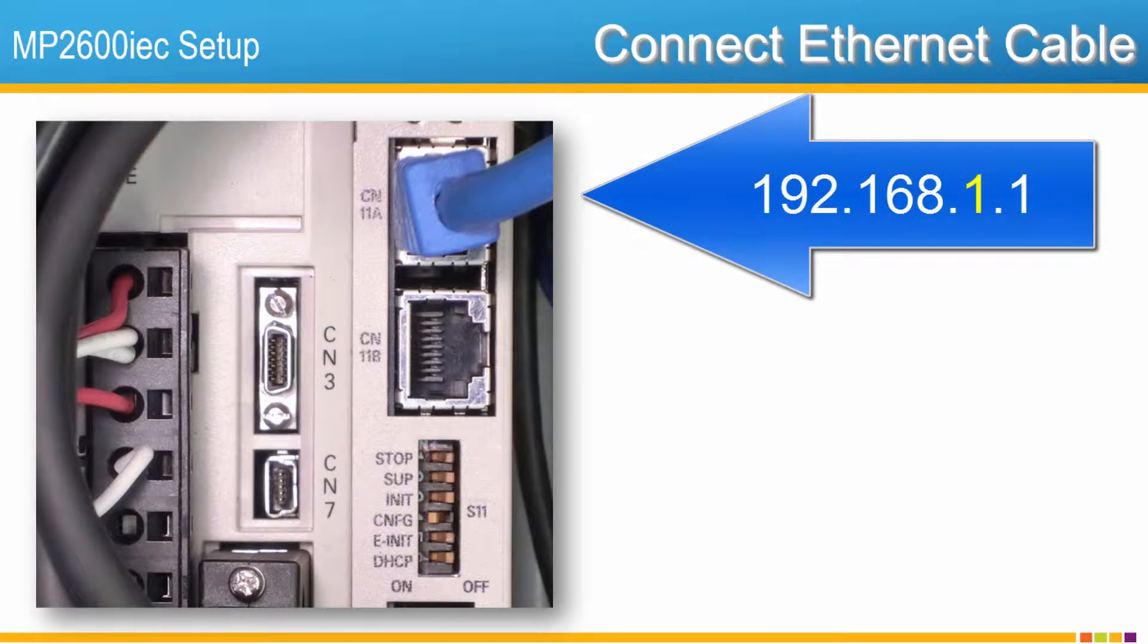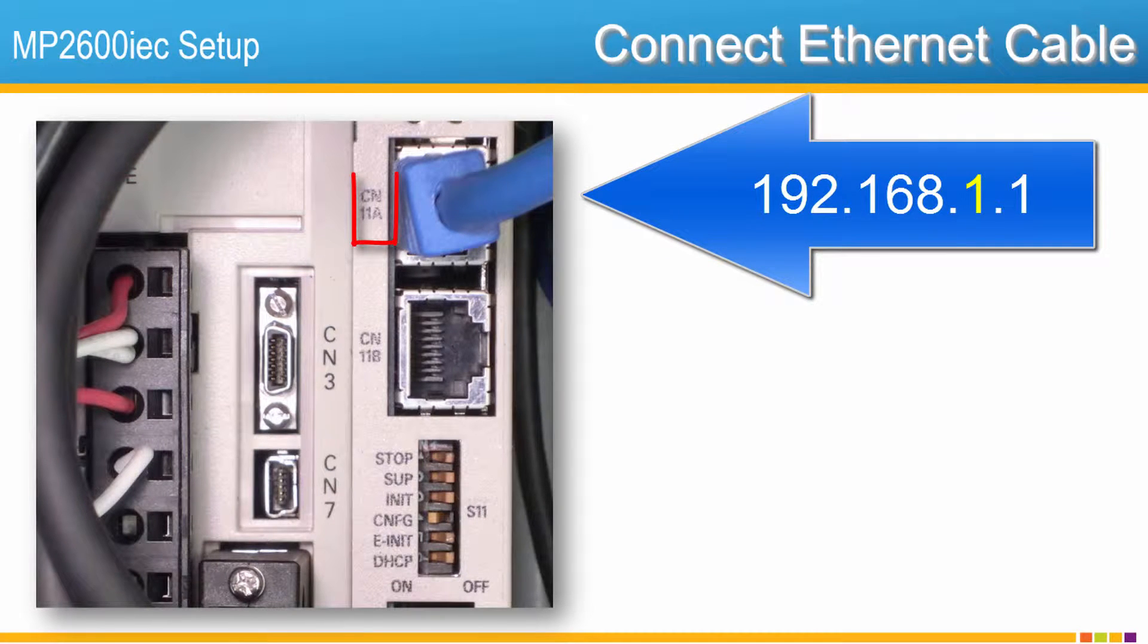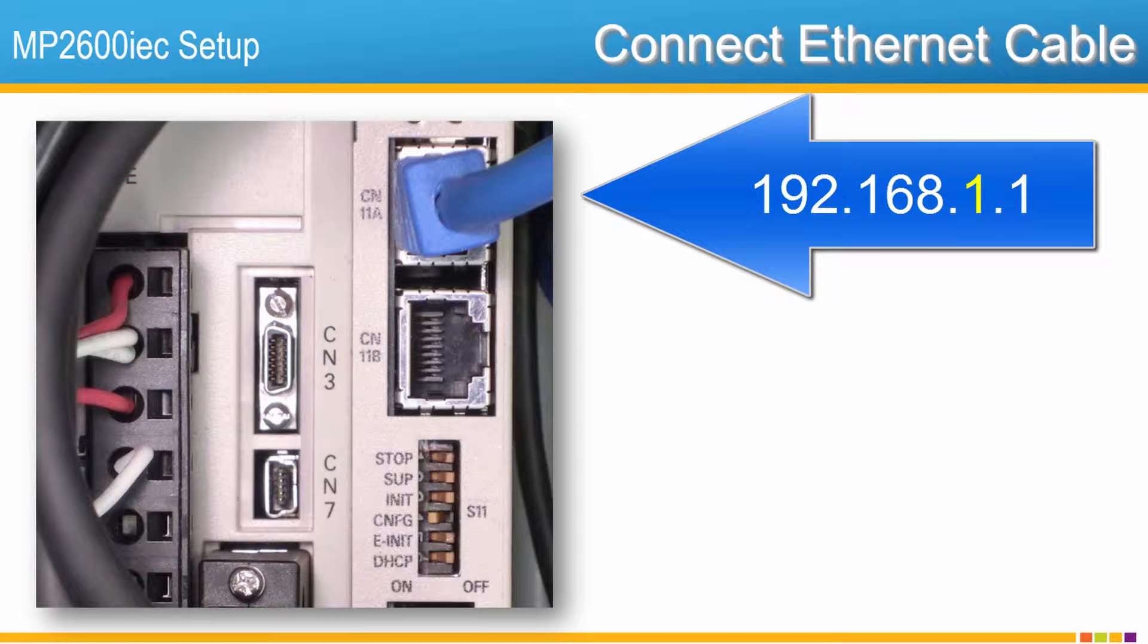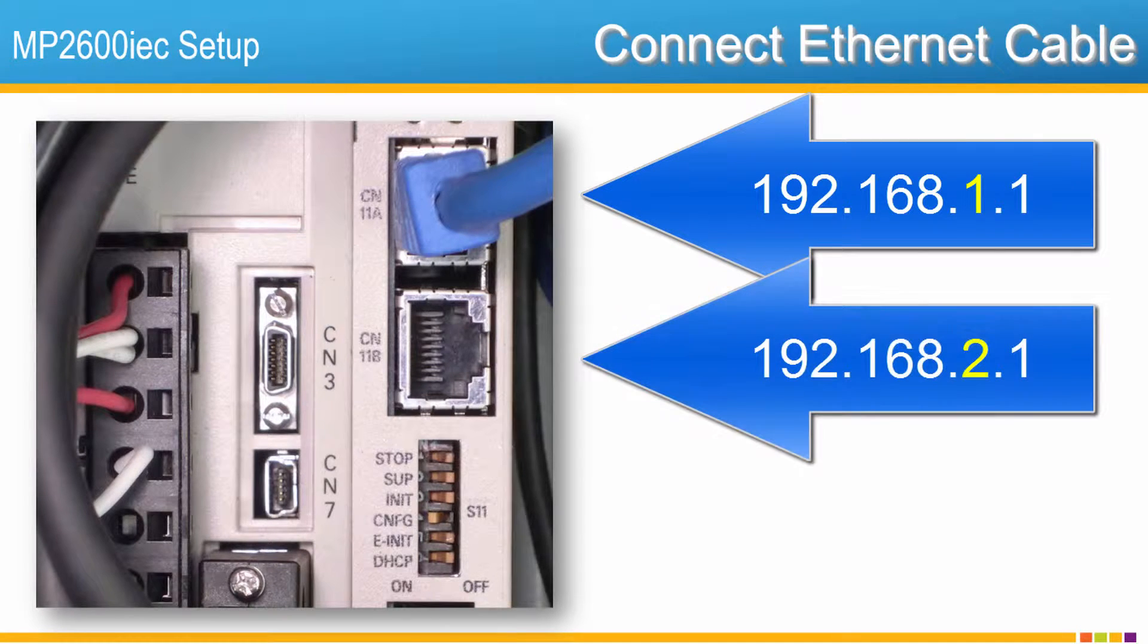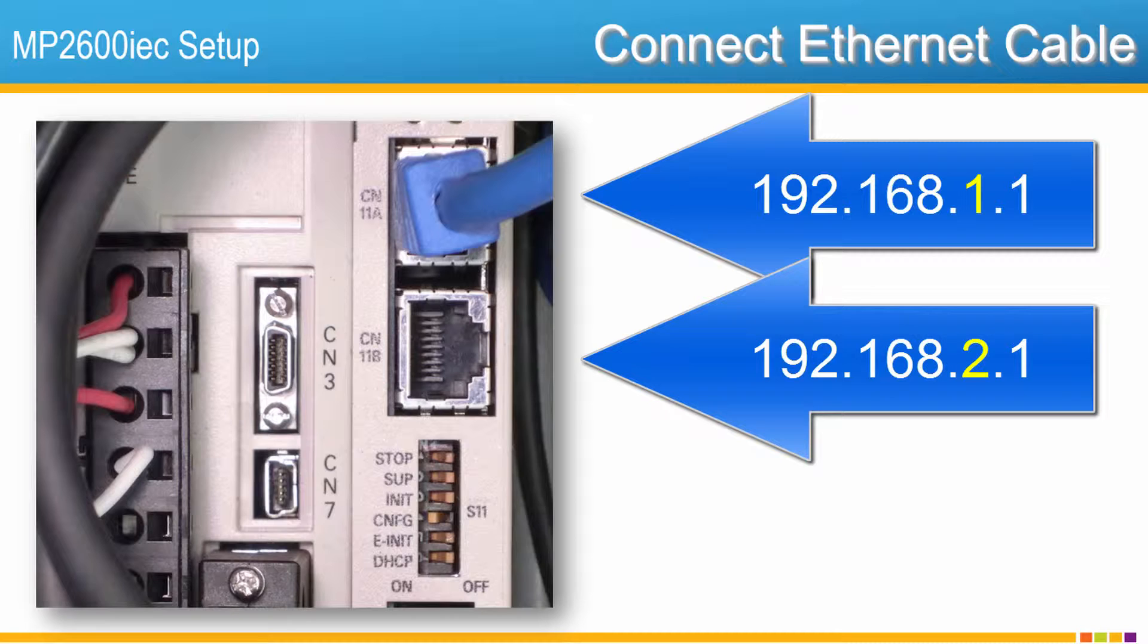Connect an Ethernet cable between the PC and controller port CN11A. A new controller has the default IP address 192.168.1.1 on port A, and 192.168.2.1 on port B.